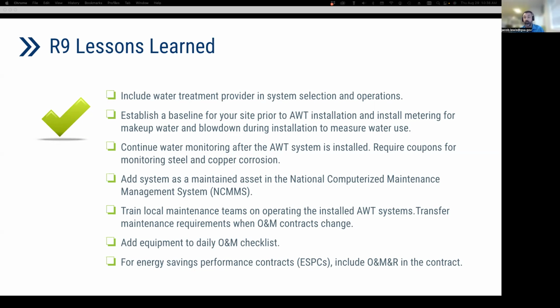And the last thing I really want to touch on is we've also changed our daily operations, where throughout our building, we have our mechanics check every mechanical space, every piece of equipment, chillers, boilers, all that. We made sure that was added to our daily checks, where our mechanics physically look at it every single day to make sure there aren't any alarms. We want to make sure that there aren't any leaks. We want to make sure the chemicals are being maintained. So your day-to-day operations do need to be altered a little bit.